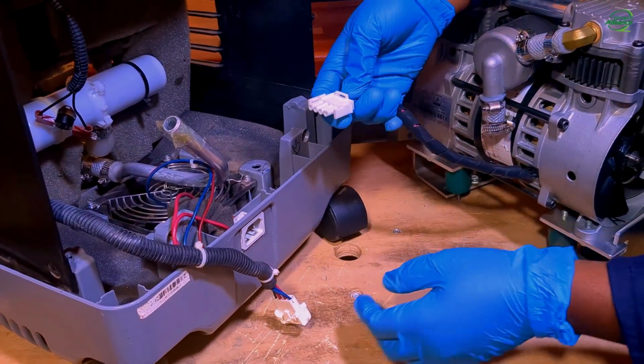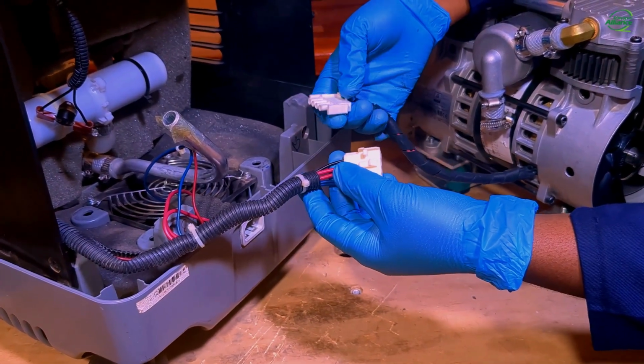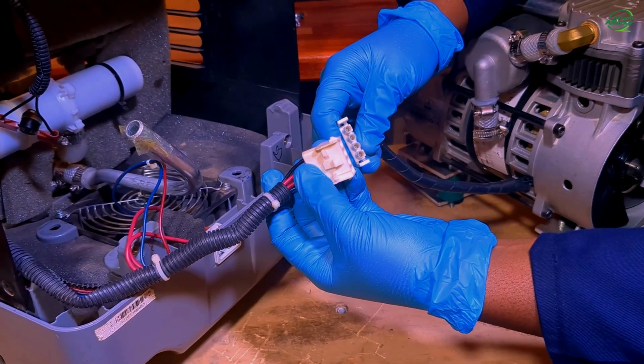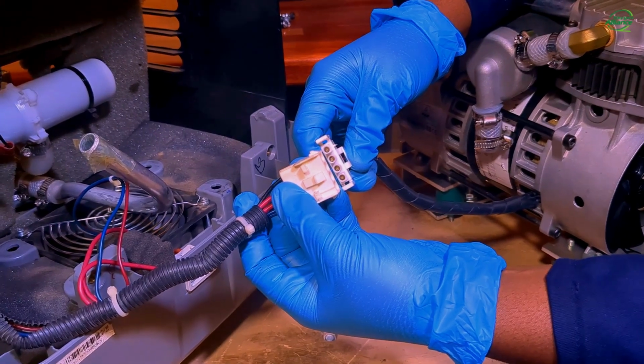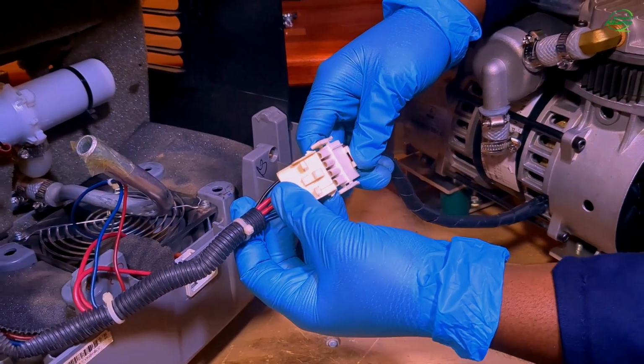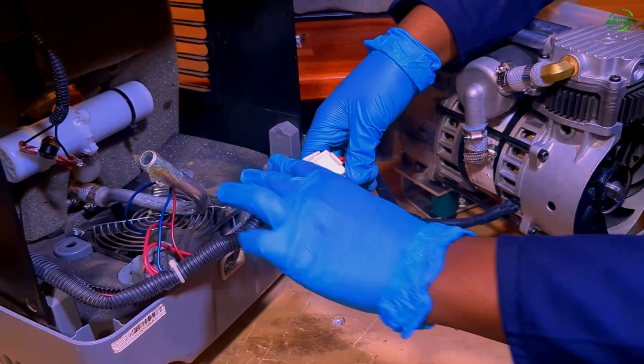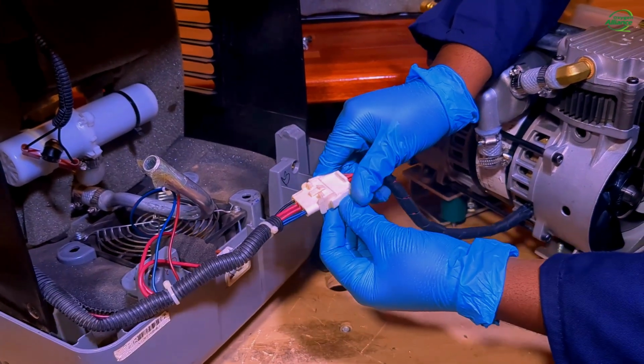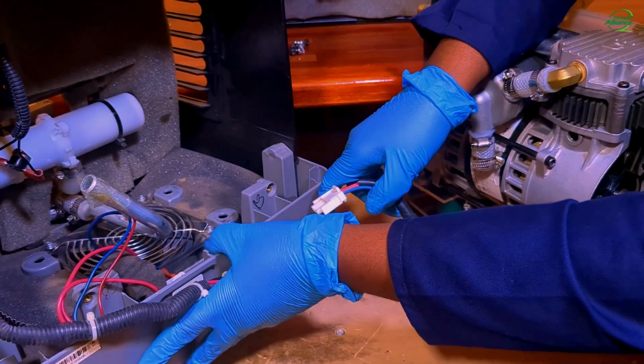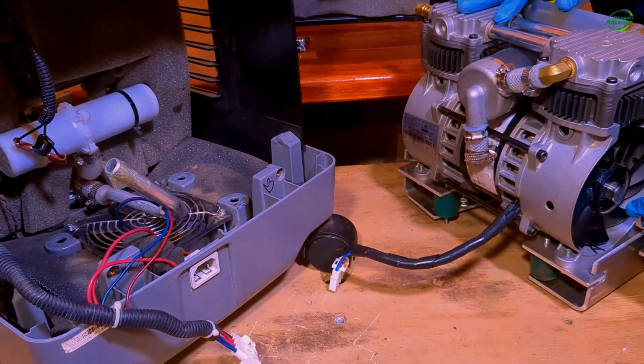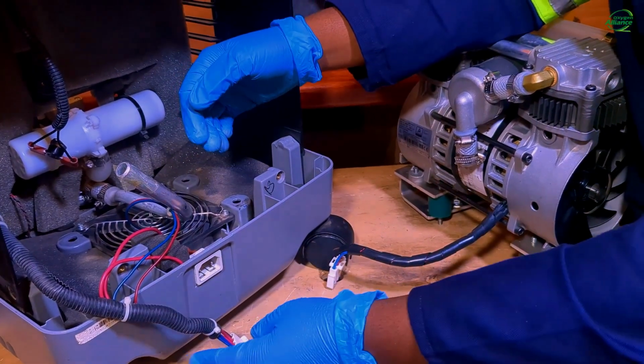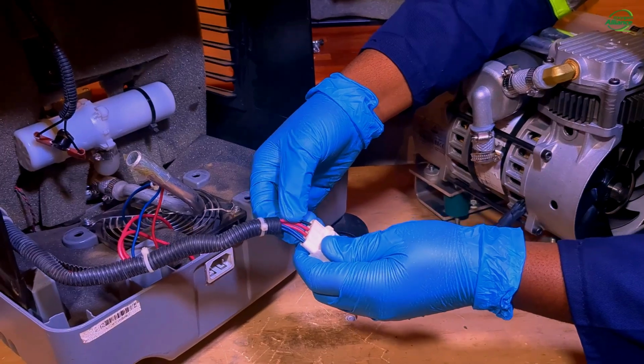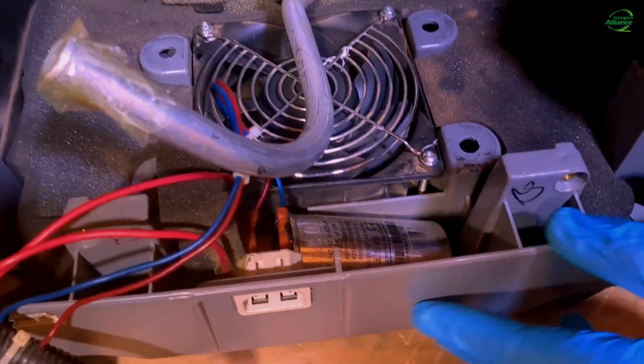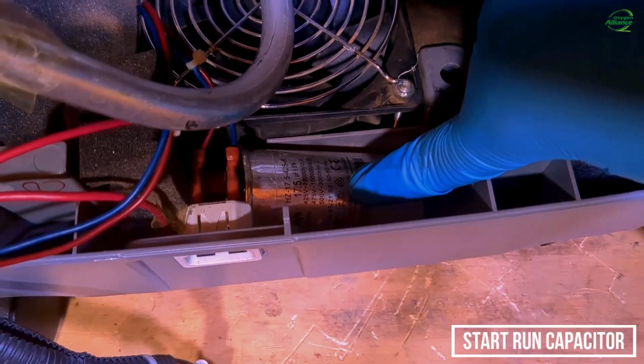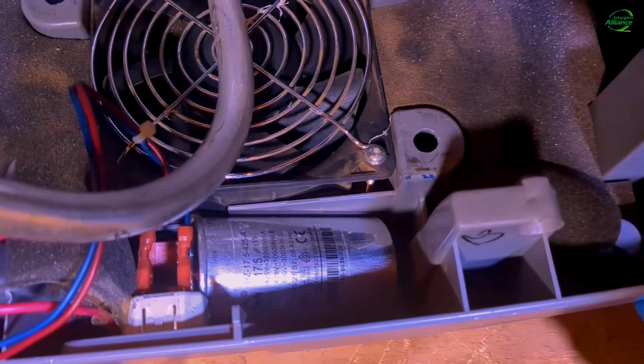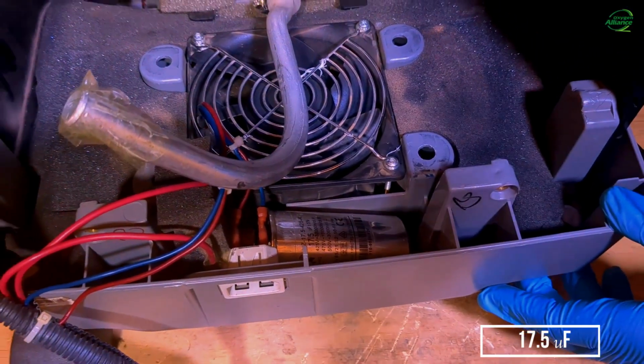So to supply power to the compressor, you connect this connector and the compressor connector. So as you can observe, the connector has different shapes, which will help you to make the right connection. So that is how you place it in. And to remove it, you just press on the sides and take it out. So on this connector, you have these two wires that supply power to the start capacitor, which is located under here. And its value is 17.5 microfarads.